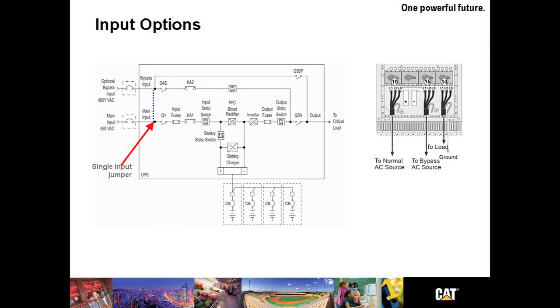Let's talk for a moment about input options. The drawing on the left shows a one line of a dual input system, which is standard. The single input configuration is depicted by the use of that dashed blue line. The image on the right shows the input connections of a dual input system. You see number 16 is Q1, or normal input. Number 15 is Q3BP, or the bypass input. Number 14 is Q5N, or the output. A single input system would only have cables connected to number 16 and internally jumpered to the correct inputs.